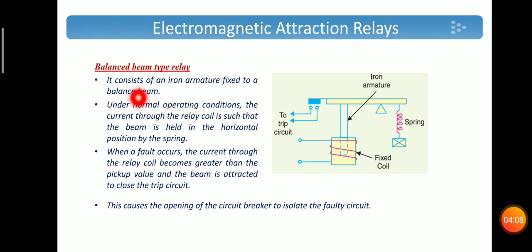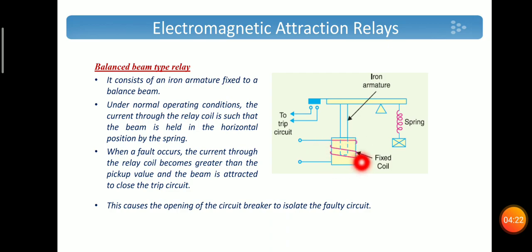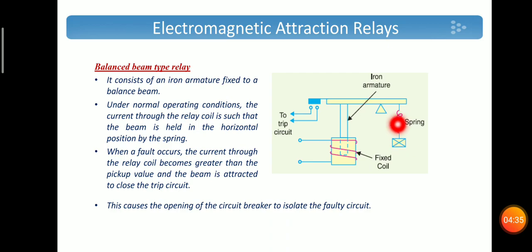The next type is balanced beam type relay. It consists of an iron armature fixed to a balanced beam. Under normal current condition, the current through the relay coil is such that the beam is held in a horizontal position by the spring arrangement. When a fault occurs, the current exceeds the pickup value, the balanced beam is attracted towards the electromagnet, closing the trip circuit and hence operating the circuit breaker.